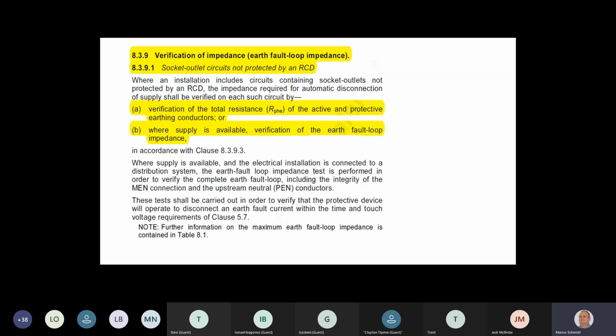Because you want to make sure, according to 5.7 of 3000, if there's an earth fault, all sockets must operate within 0.4 of a second. Can you remember 0.4 of a second? Yeah. What trips faster than that? A circuit breaker or an RCD? RCD. RCD is 0.3 of a second. Right. So guys, if you read through this, you must keep your MEN link in. Everything must be normal as in operational conditions.